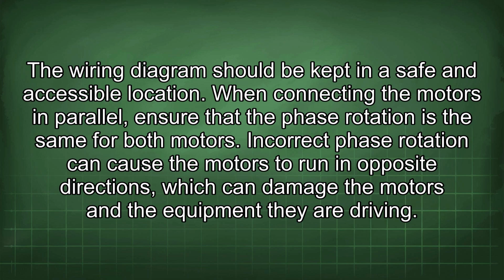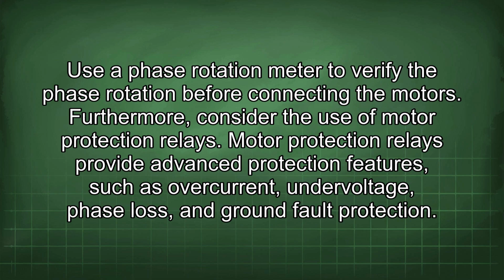When connecting the motors in parallel, ensure that the phase rotation is the same for both motors. Incorrect phase rotation can cause the motors to run in opposite directions, which can damage the motors and the equipment they are driving. Use a phase rotation meter to verify the phase rotation before connecting the motors.